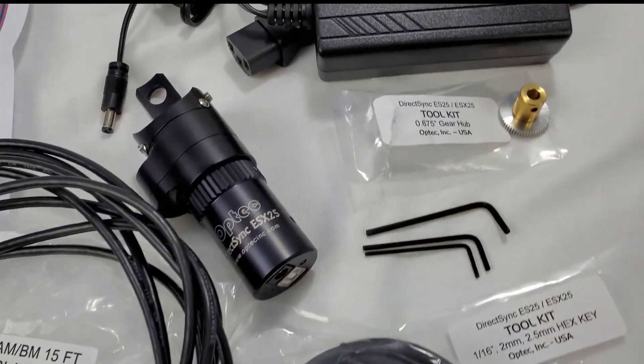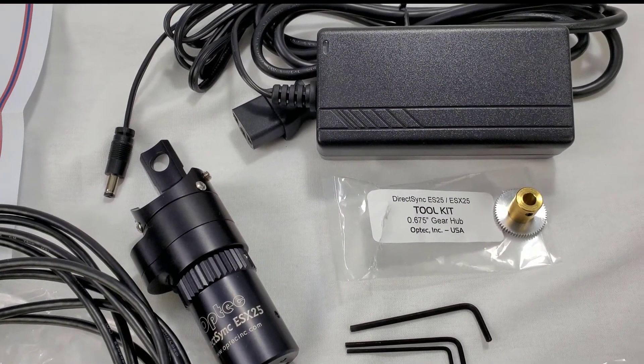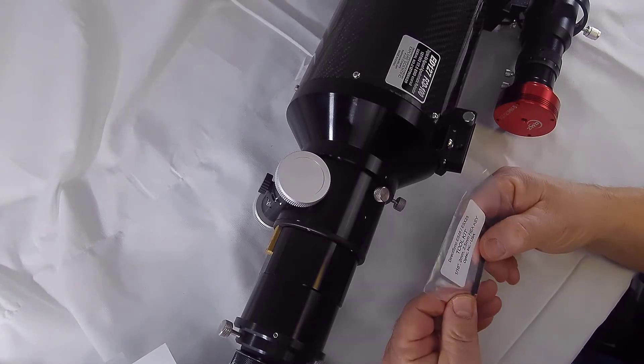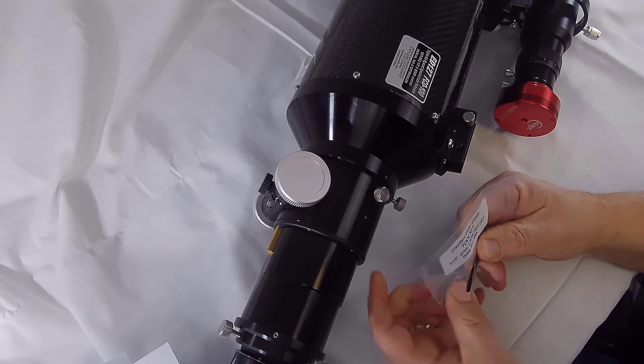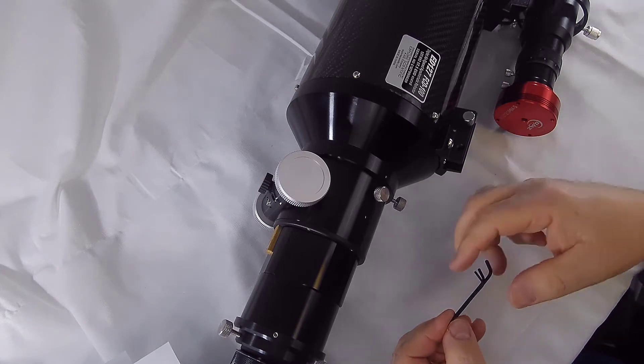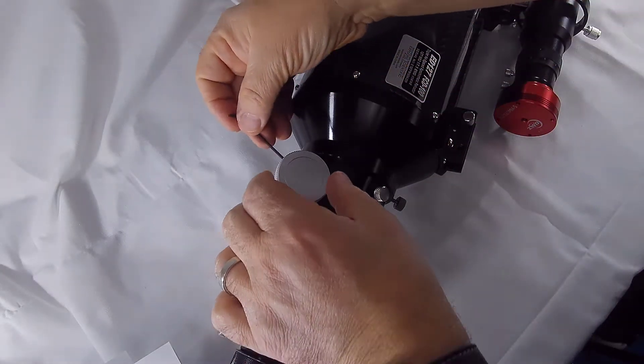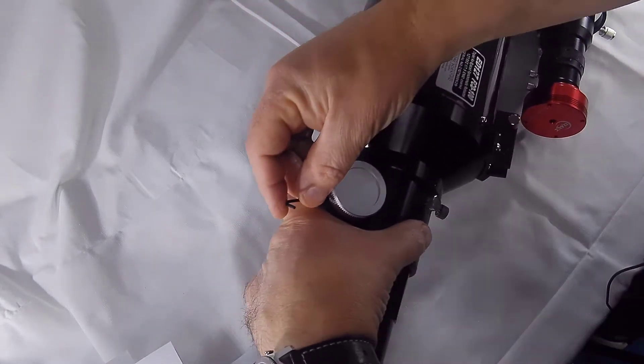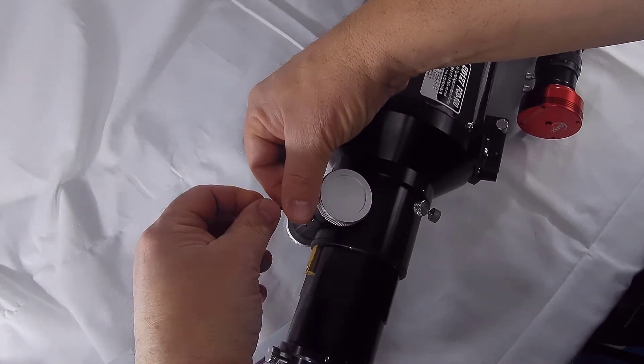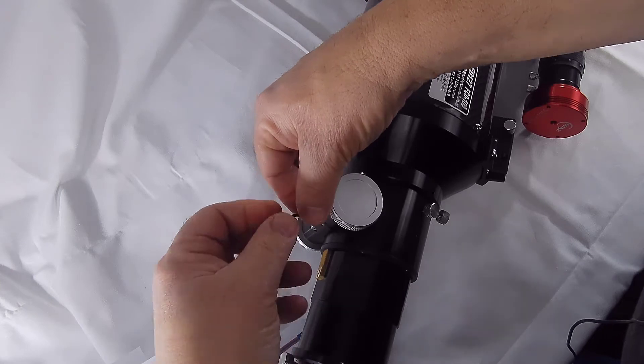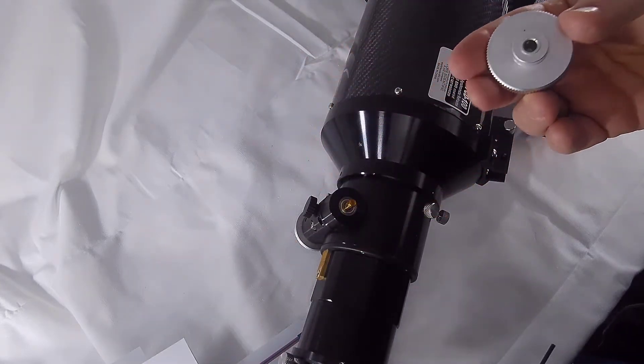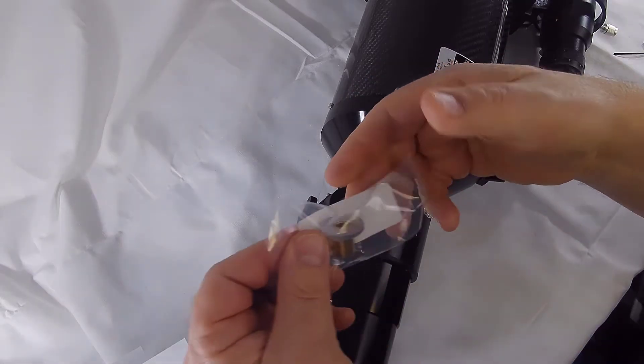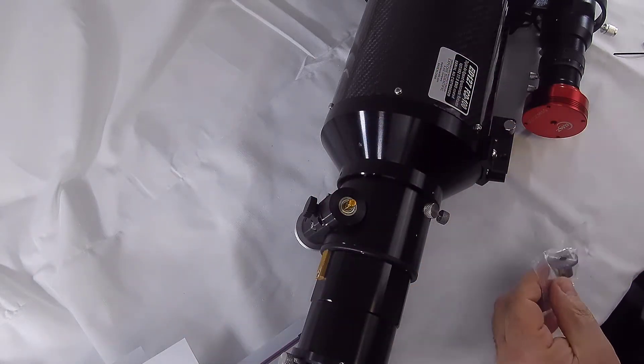Alright, so to add this we're going to take the included allen wrenches. There's three different ones for removing the coarse focus knob, adding the gear, and then the third will be the set screws to mount the focus motor. So the first thing I'm going to do here is remove the coarse knob off the focuser. That's just one allen wrench, just a quick couple of turns and that should just slip right on off. Here you're gonna see the exposed shaft where we're gonna add the gear.